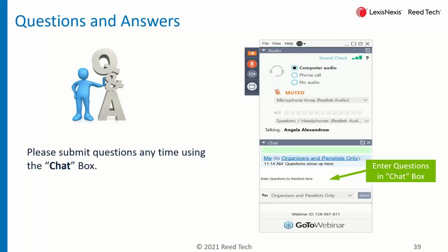Yeah, absolutely. So a lot of times the contract manufacturers are unsure at first whether they have responsibility to do the submission, but really the FDA calls out very specifically, Gary, that it's a labeler or relabeler that has that responsibility to submit the data to the FDA's GUDID.